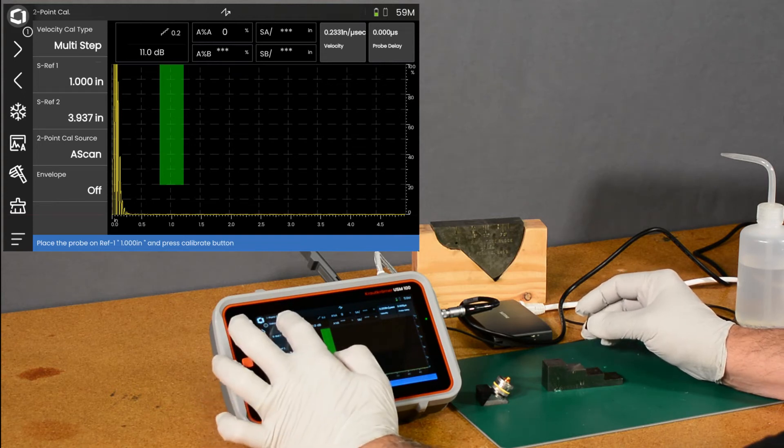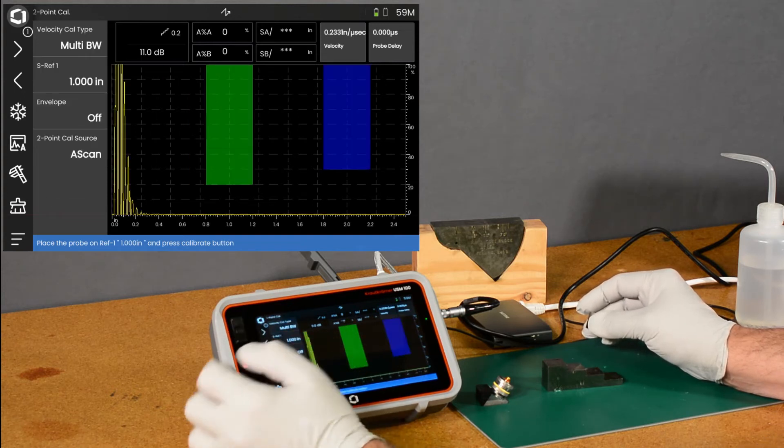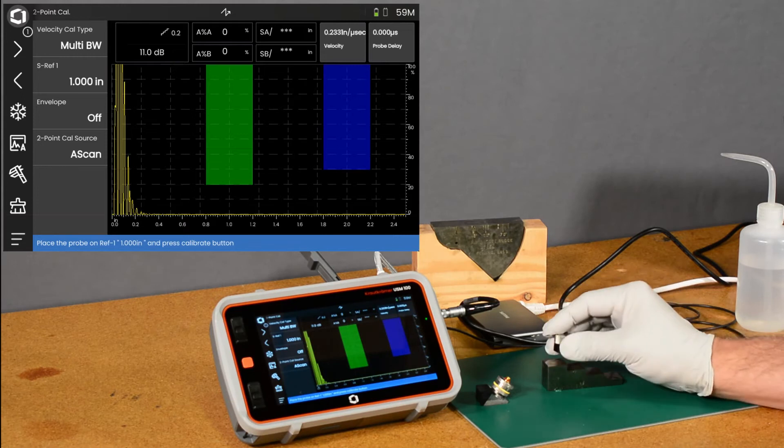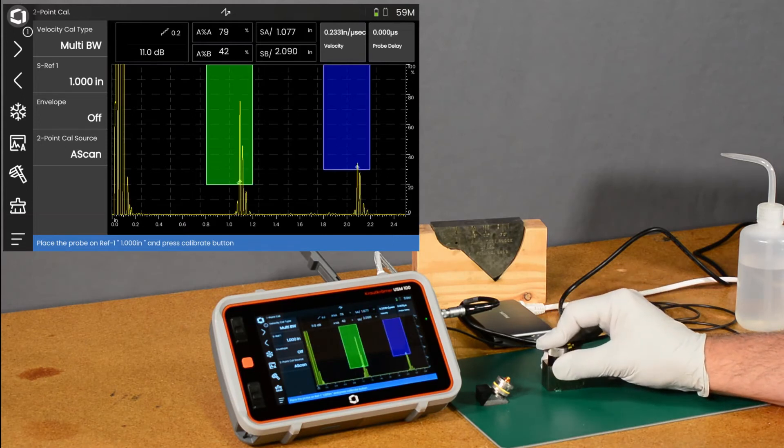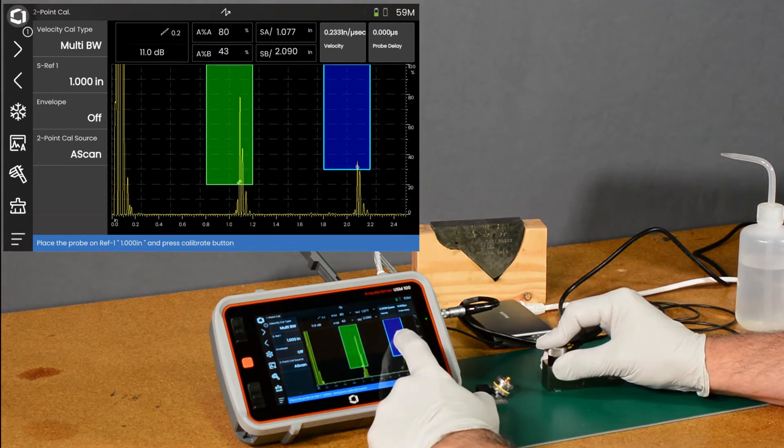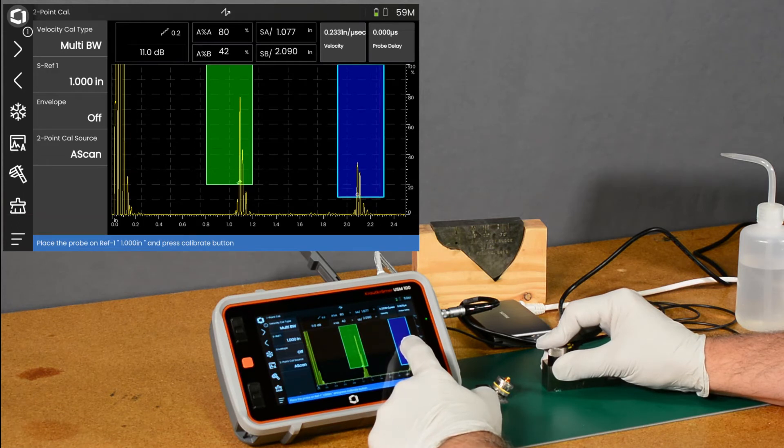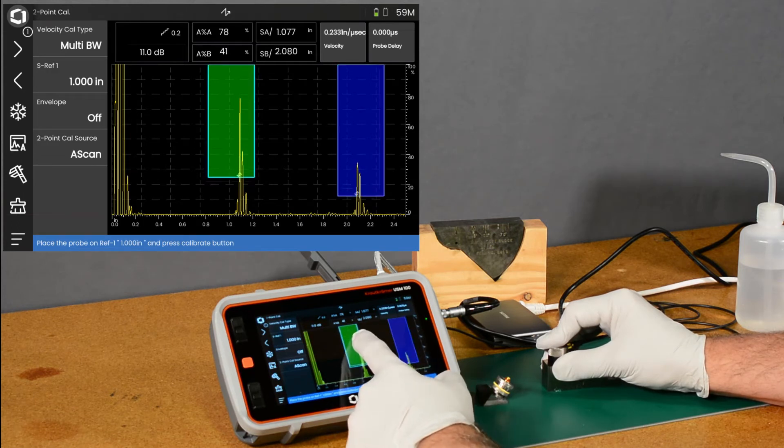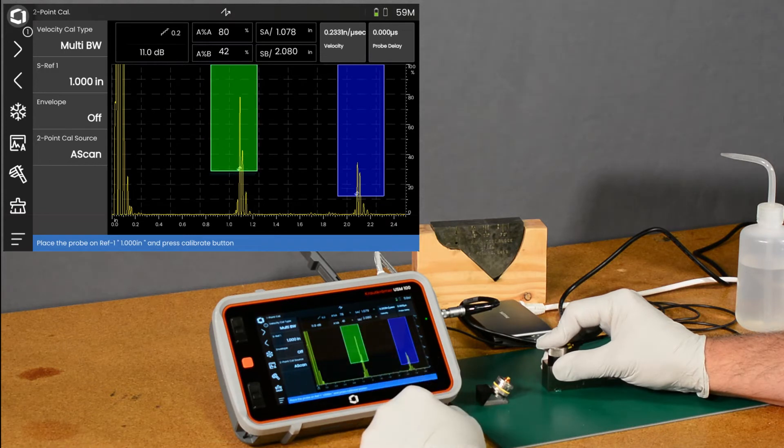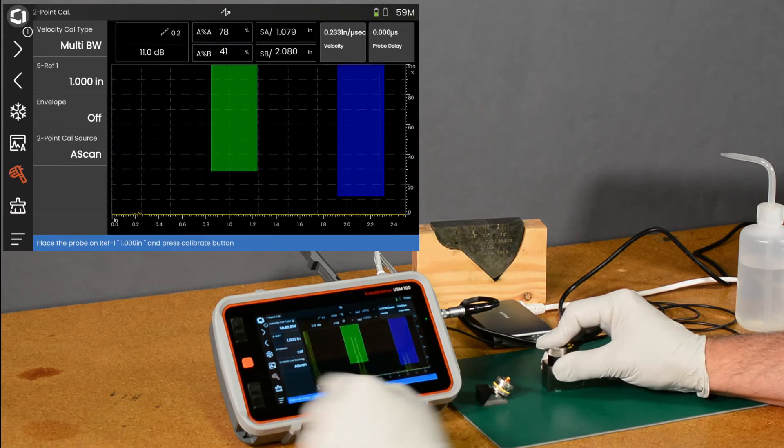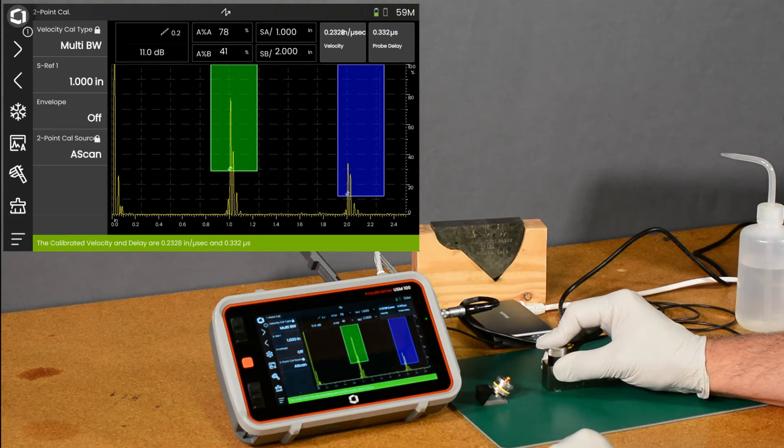And I'm going to make use of our multi-backwall calibration. So this allows us to do the calibration in one quick step. I'm going to drag my gate B here so it's about the same place on the flank as gate A.